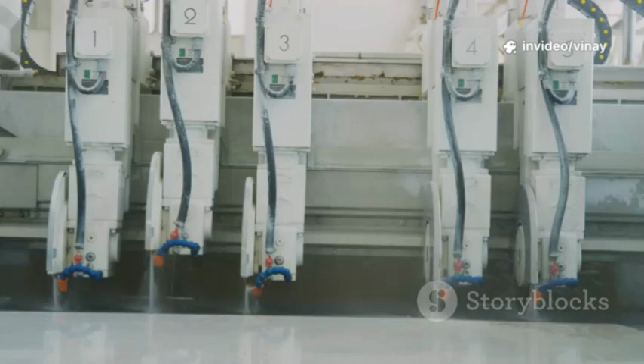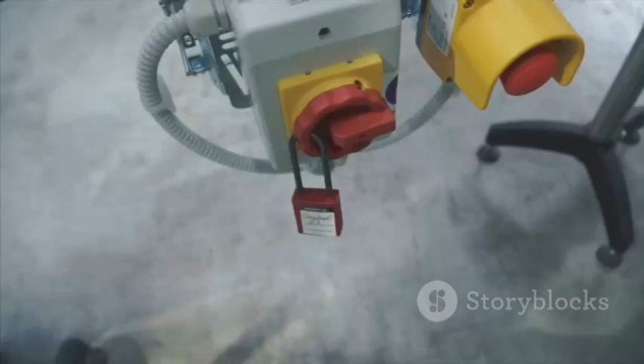These tests are done without real product, focusing on the machine's operation. For example, a filling machine's pump speeds and safety features are checked at all settings. Results are documented in an OQ report, confirming the equipment operates safely and precisely. A successful OQ gives confidence in the machine's controls and reliability.